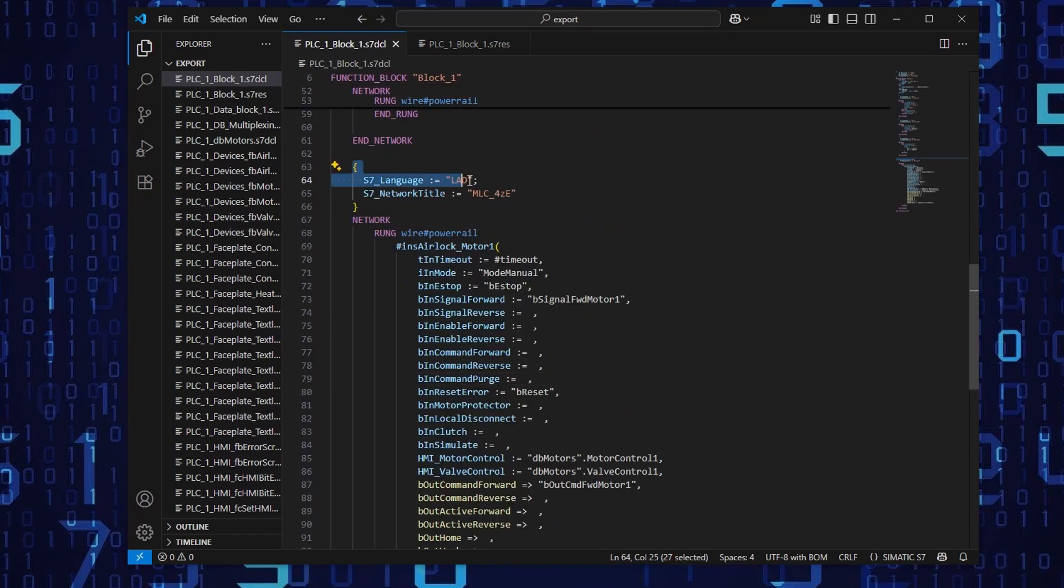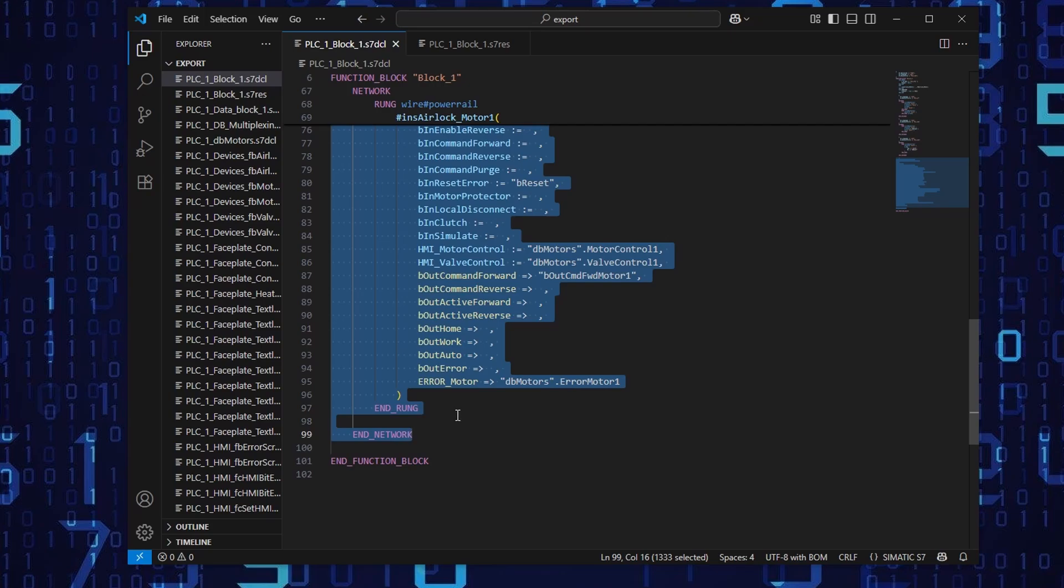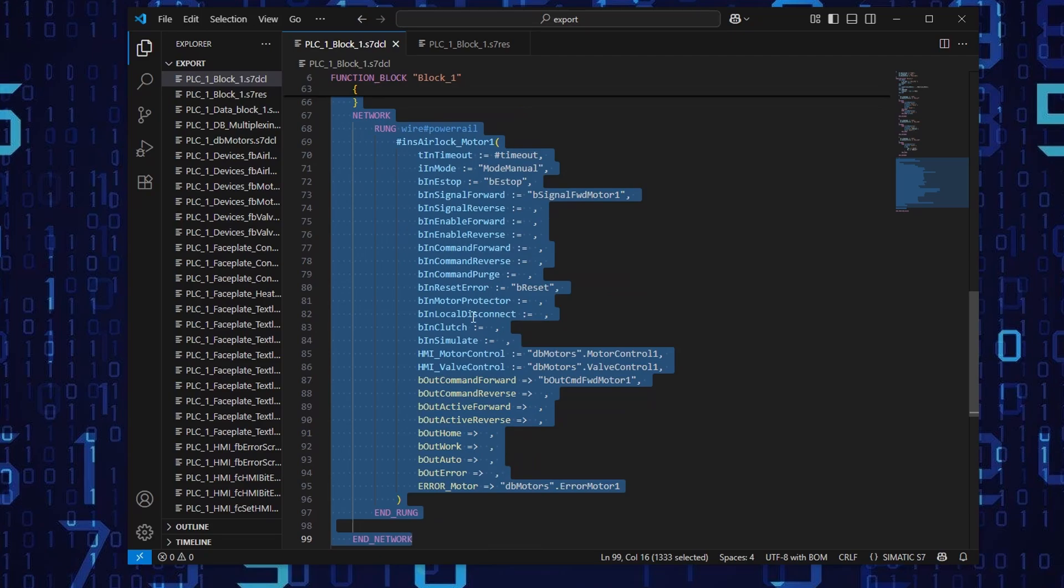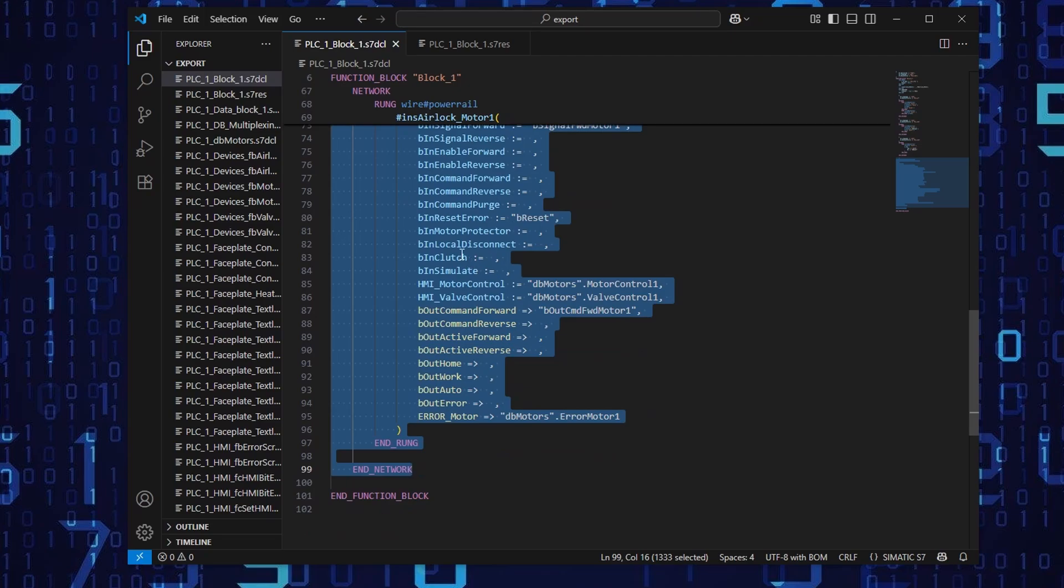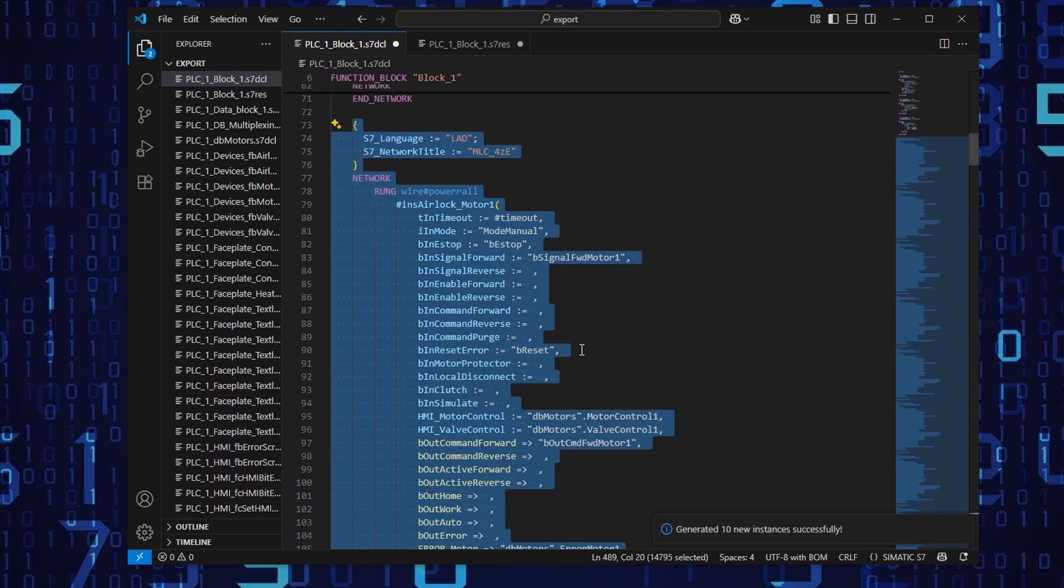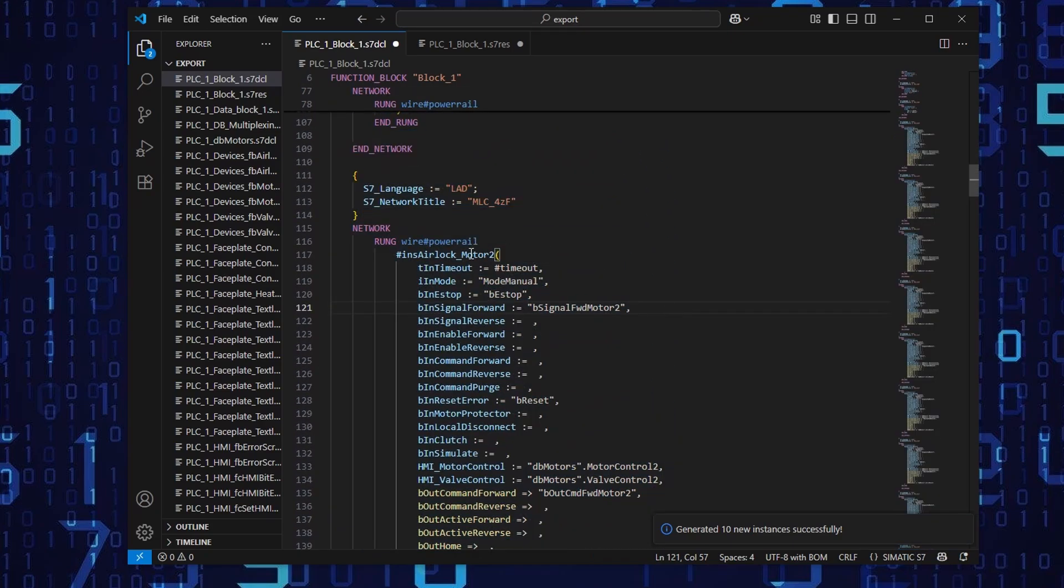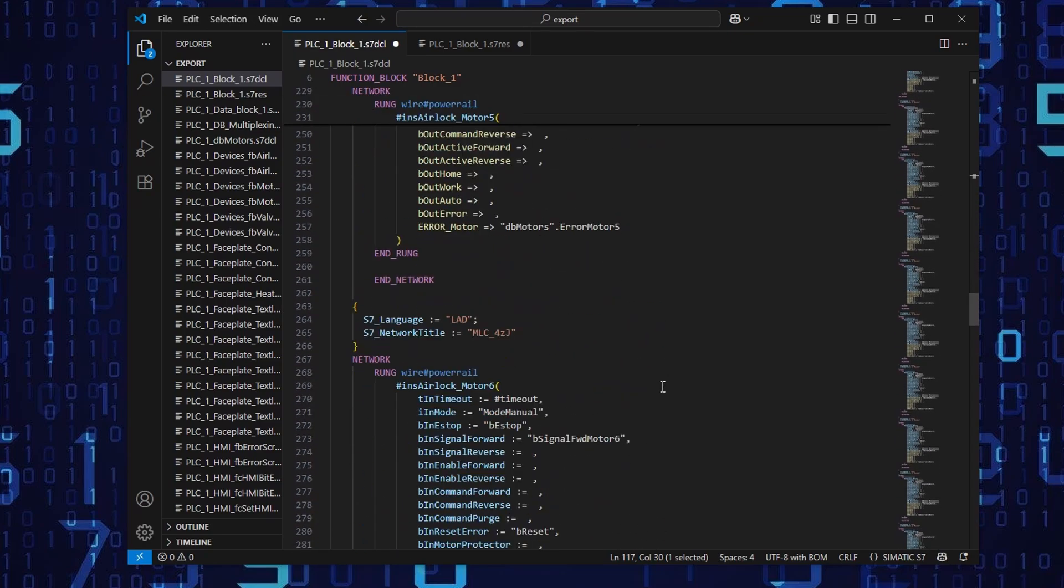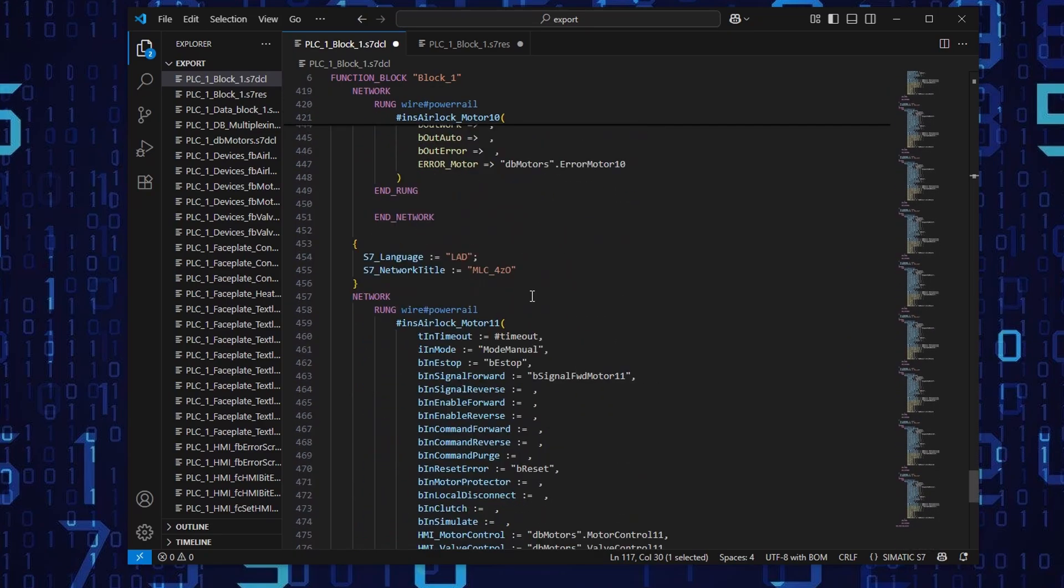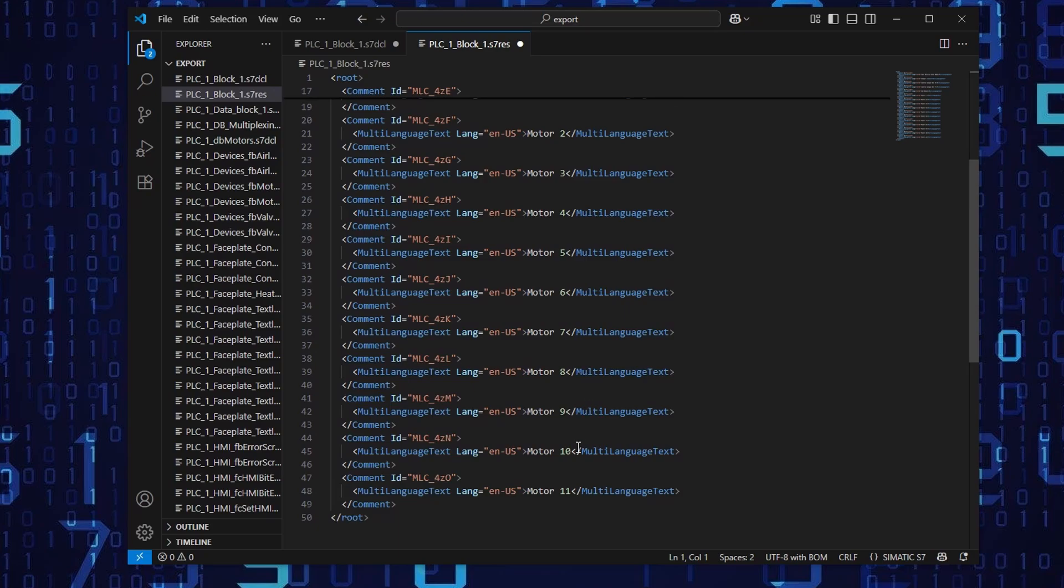And another feature here. Let's say we would like to have more instances of the motor block, and instead of manually doing and connecting them as I have an example here, I'm going to select it starting before the block with the command language and the block. And then right-click and just select generate function block instances. I'd like to create 10 more instances. And you can see that they have been generated successfully. All of the tags also increment the names, so it will match our structure in the data block. The network titles are automatically generated. And in the other file, we can also see the network commands.